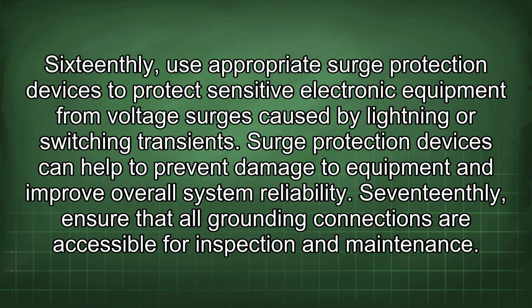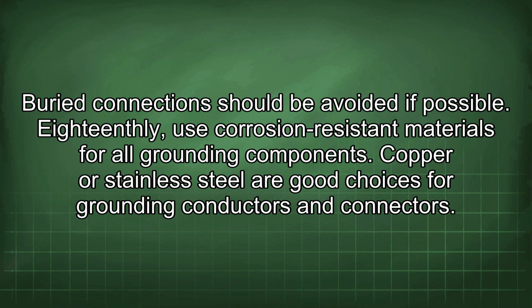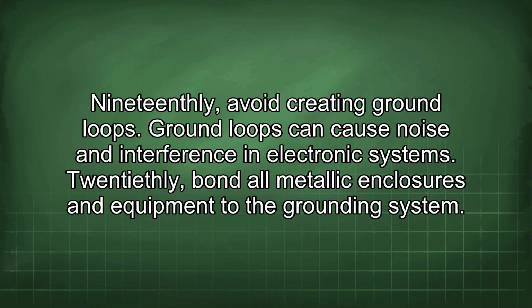17thly, ensure that all grounding connections are accessible for inspection and maintenance. Buried connections should be avoided if possible. 18thly, use corrosion-resistant materials for all grounding components. Copper or stainless steel are good choices for grounding conductors and connectors. 19thly, avoid creating ground loops. Ground loops can cause noise and interference in electronic systems.